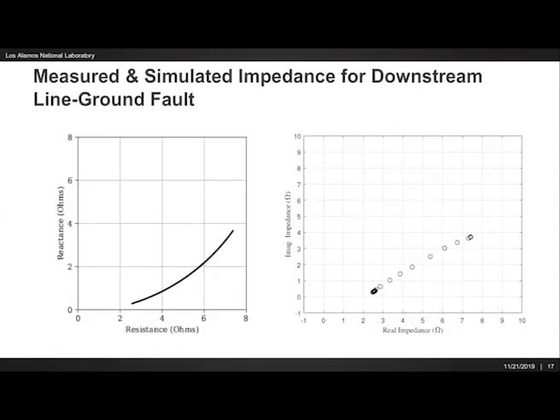Fortunately, as I show analytically and in simulation, current compensation for distance protection is robust against unbalanced operating conditions, so it's able to correctly calculate the impedance between the relay and the fault under both analytical and simulated cases.